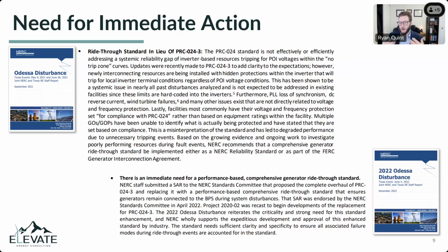These IBR facilities have introduced new challenges where we're tripping on PLL loss of synchronism and reverse current flows, turbine failures, uninterruptible power supply failures, phase jump protection settings, overcurrent protection. All of these different forms of protection are now tripping these facilities, or have tripped these facilities in the reports that have been written. We now need to revamp our requirements to make sure we capture the same essence of what we were shooting for 10-plus years ago, when the system was predominantly synchronous generator based.